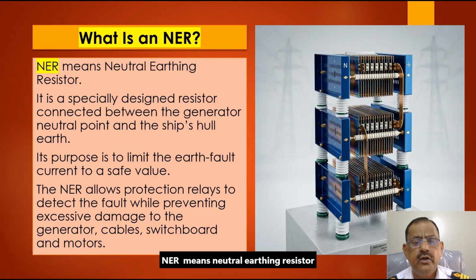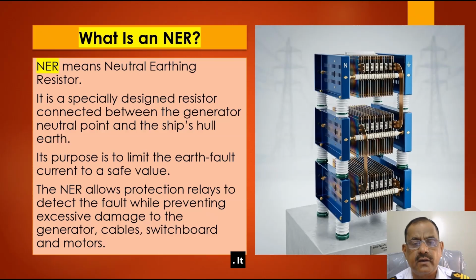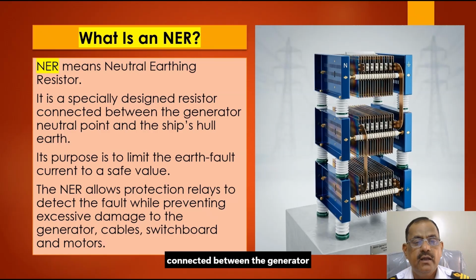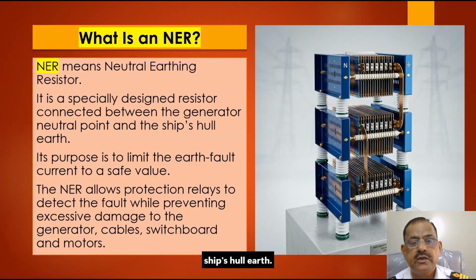NER means Neutral Earthing Resistor. It is a special resistor connected between the generator neutral point and the ship's hull earth. Its main job is to limit earth fault current to a safe value. At the same time, it helps the protection relay detect the fault correctly.